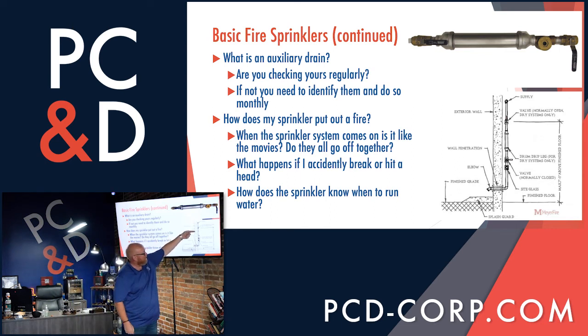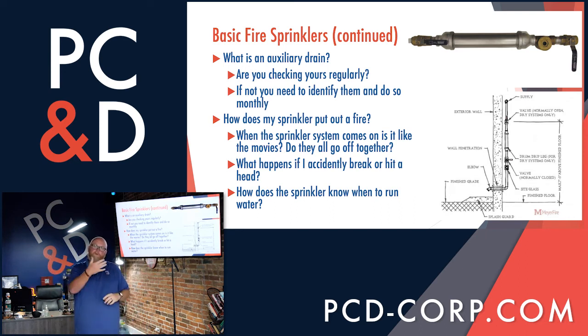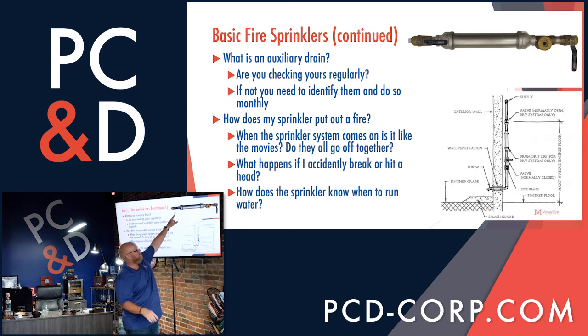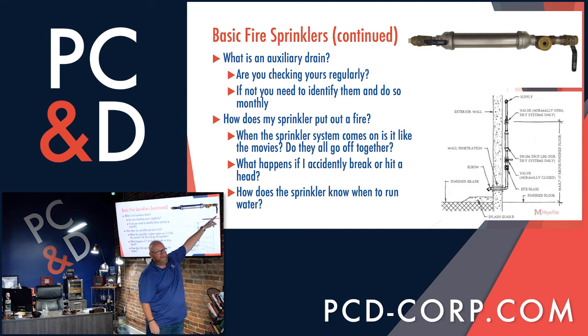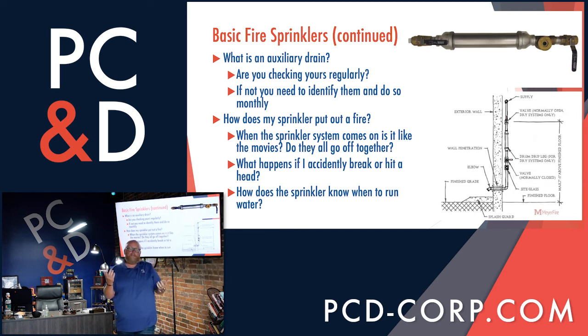So you may ask yourself, okay, I've got water working its way back, I've got water coming down into my mechanical closet or wherever this low point drain may be located, and it's filling up this valve. As you can see right here, this bottom valve is closed, okay? So your water is going to get right here and it just starts to fill this pipe up, okay? So how do you go about draining those? I can't open it, Mitch, because if I open it, there goes my air, then I'm going to fill the whole thing with water. Yes and no. You cannot open it without closing the top valve first. You notice in the picture of the actual valve, we have two ball valves, okay? One is open, one is closed. In this situation, my water could be running into this, building up in this piece of pipe, but how do I get the water out of it?